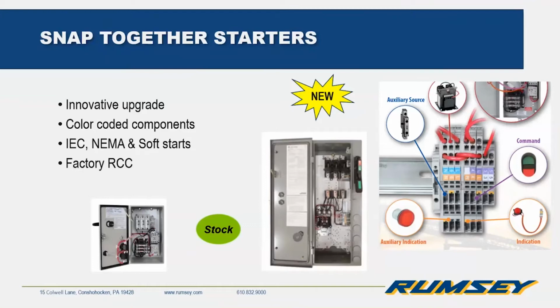color-coded. And the parts that you would plug into it are also color-coded. So if you need any auxiliaries, if you need a start-stop push button, HOA, selector switch, pilot light, whatever the application calls for, you can get those parts, and it's just plug and play. It takes about just a few minutes, 5-10 minutes, and you've got yourself a combination starter. So this is different. Nobody in the industry is doing this right now. On top of the color code, the pilot lights and switches, the plugs are keyed for a very specific way. And you can, I don't know if you can see in the picture there, but the plugs themselves are also keyed for what they plug into. So it just helps reduce any wiring errors and just to make sure it's all plugged in correctly. So this goes across all the IEC starters, NEMA starters, and soft starts.